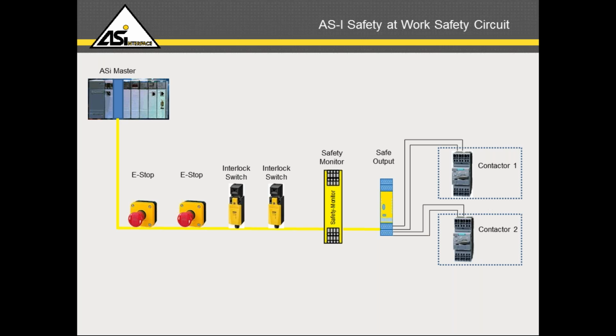So gone are all the multi-conductor cables we talked about, gone are the excessive cable trays, gone is the need for conduit, along with labeling of individual wires, the potential for errors, and the maintenance headaches. We now have all of our I/O devices, safe and standard, sitting on a single cable, and communication to the PLC is also on that single cable. So everything's on one 2-wire cable. Further, mapping into the PLC is simplified. The ASi master presents the network's data as simple I/O into the PLC data tables.